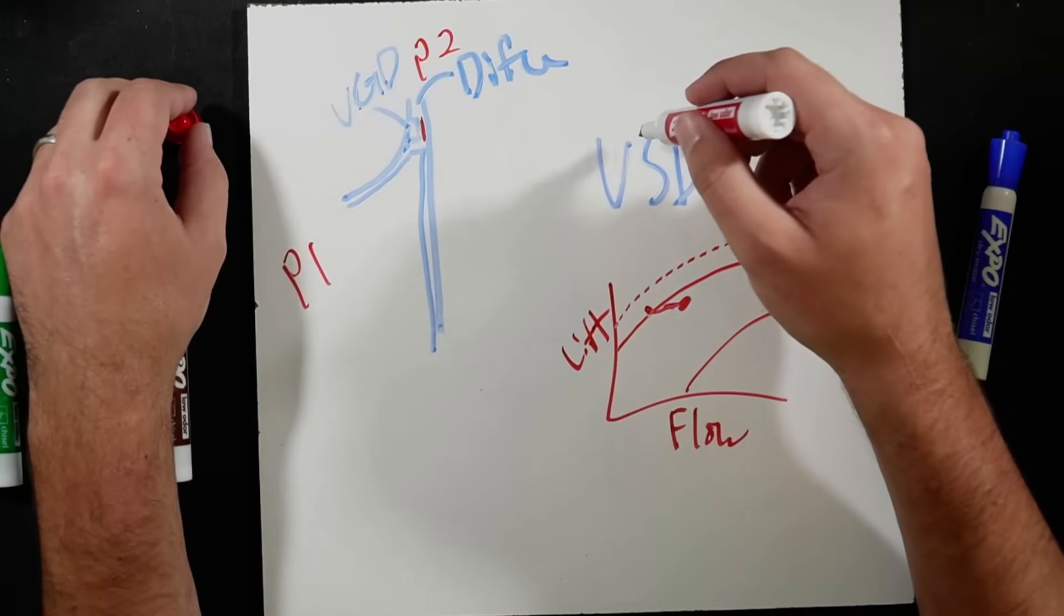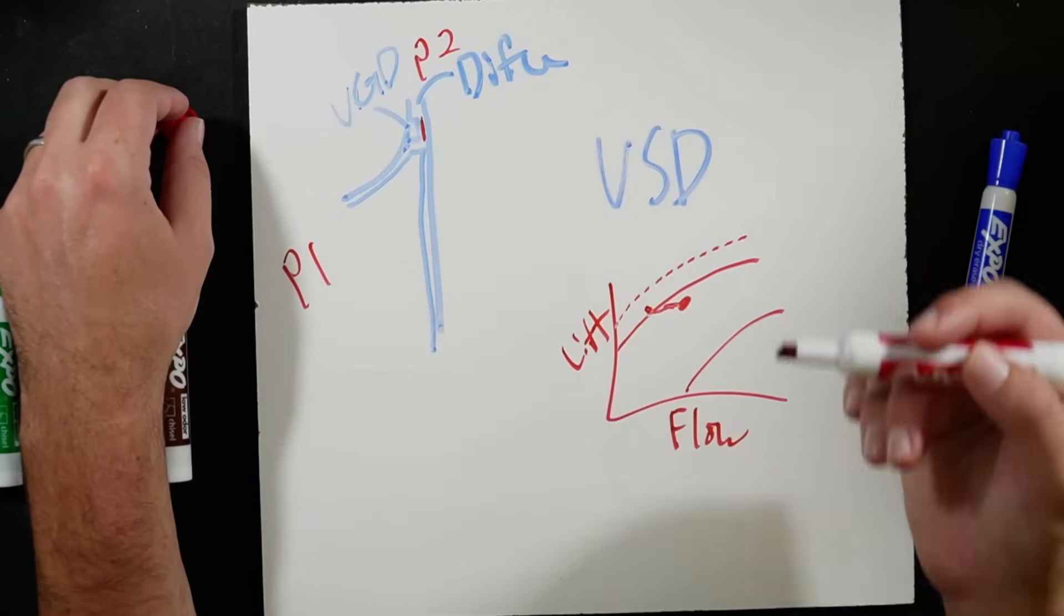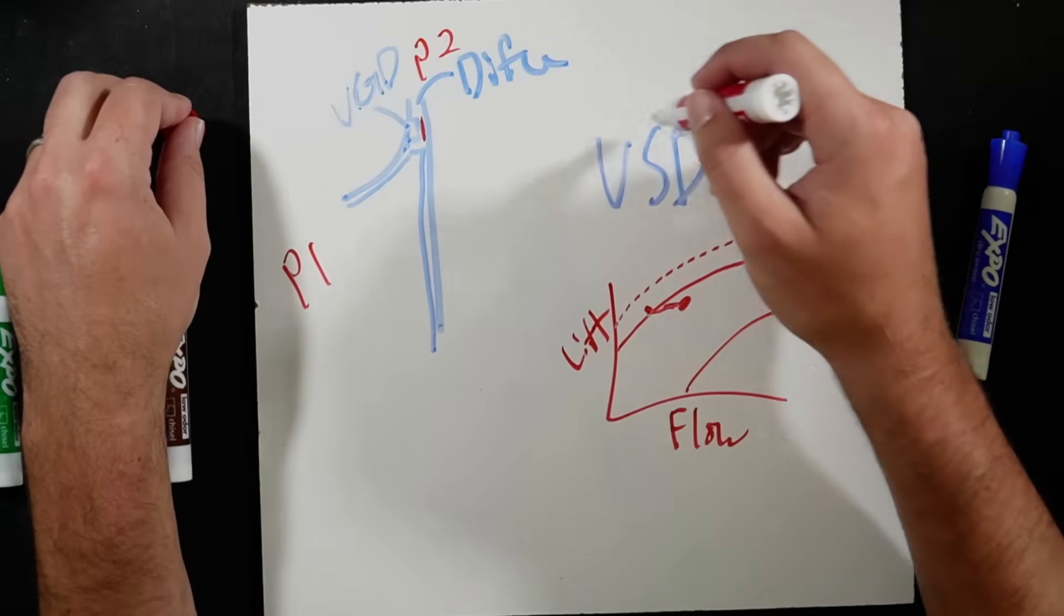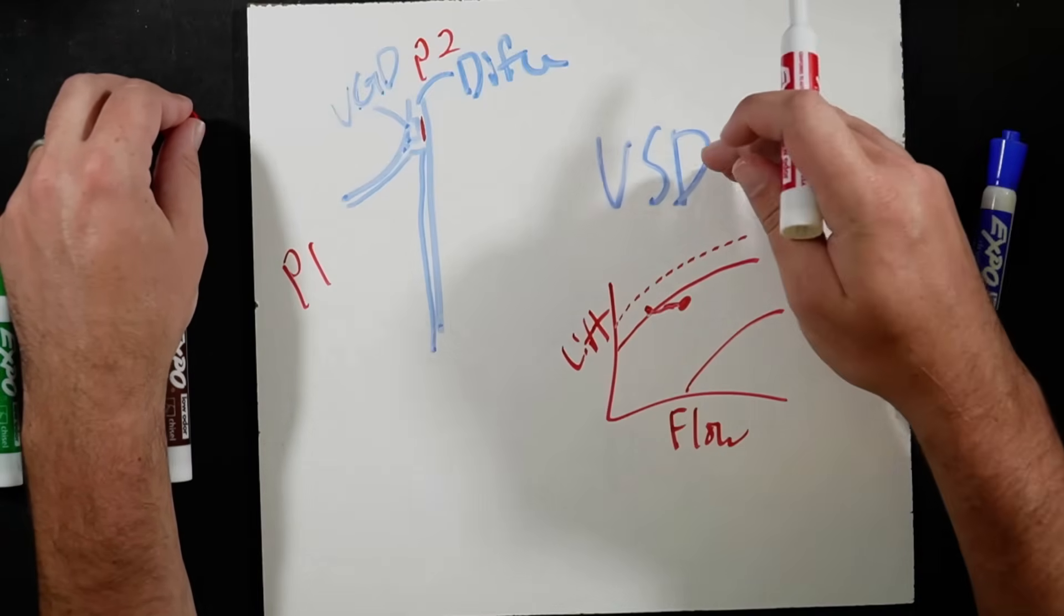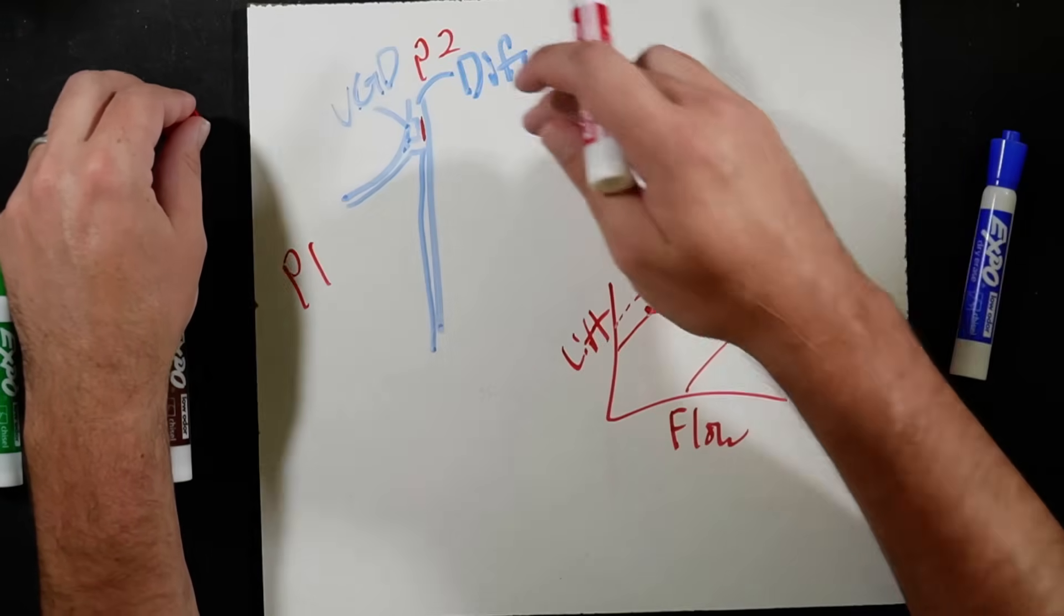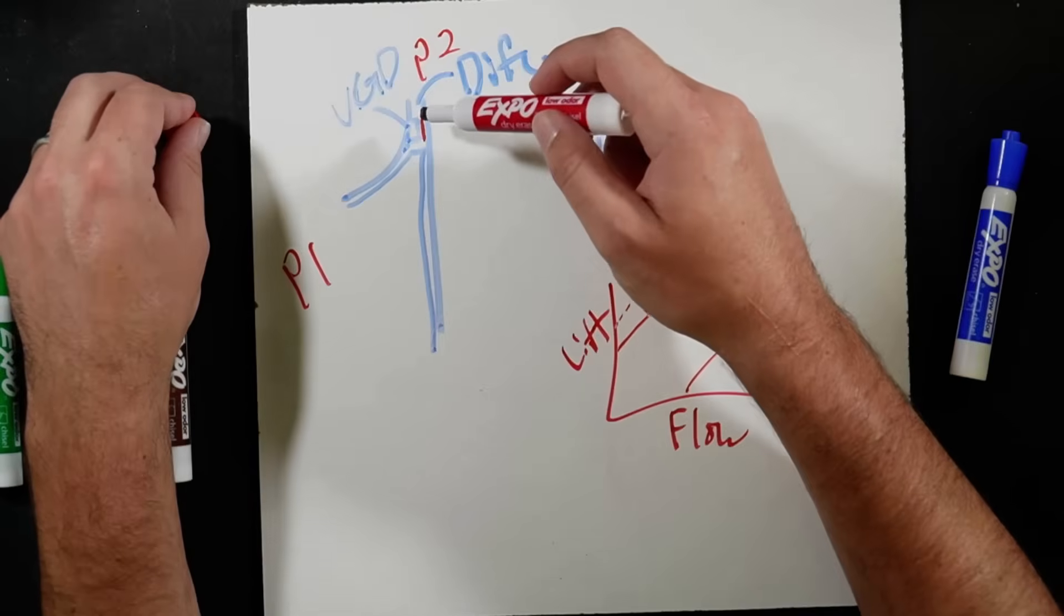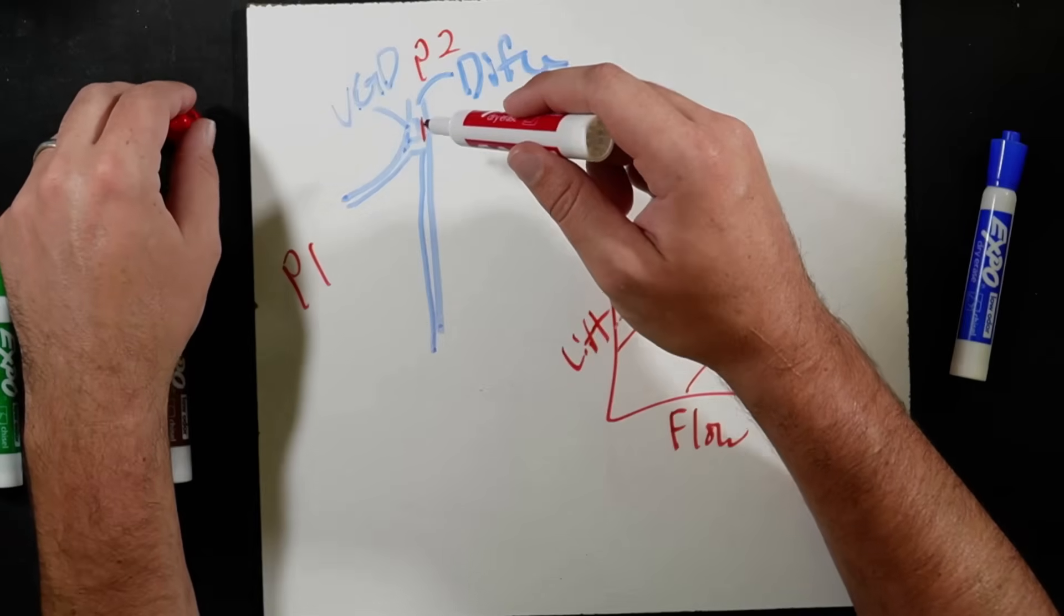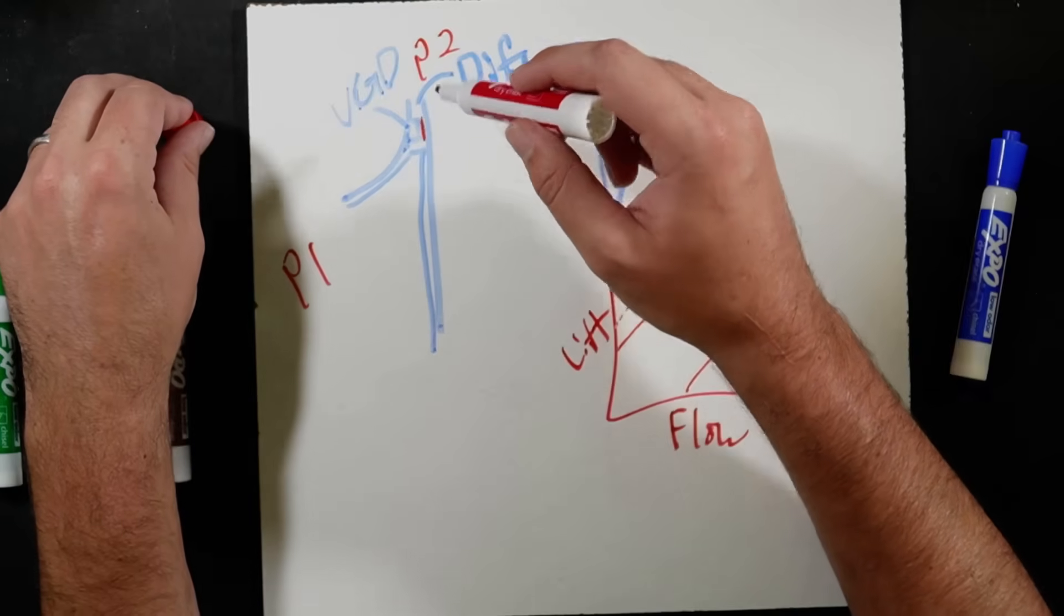So in the event that we're running at a part load, but we're not trying to fully unload, the VSD is still the primary load and unload mechanism, meaning speeding up or slowing down the compressor is still the main way we're controlling load. And the VGD at that point, its main job is to prevent the surge and stall condition by modulating this diffusion gap.